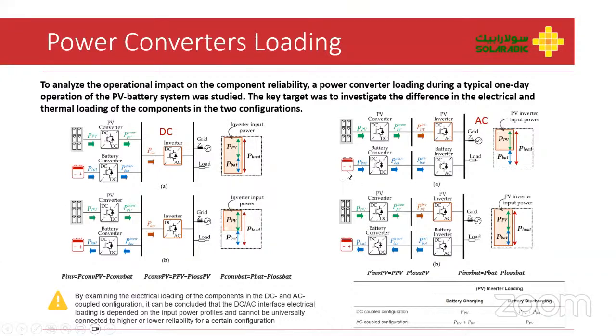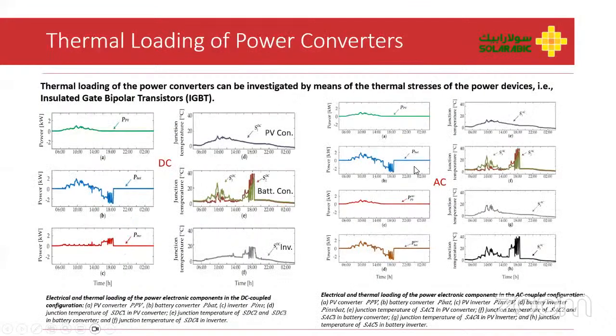But if you categorize in terms of the charging and discharging of the batteries, there is a big difference in terms of the loading of the power converters. Similarly, we then proceed to the thermal loading of the power converters. In order to understand that, we need to investigate the thermal stress that the power electronic devices, for example the IGBTs, within the inverters have to go through during these specific loadings. On the left, we have the graphs for the thermal loading of the power devices in the DC coupled configuration, and on the right, we have the graphs for the AC coupled configuration.